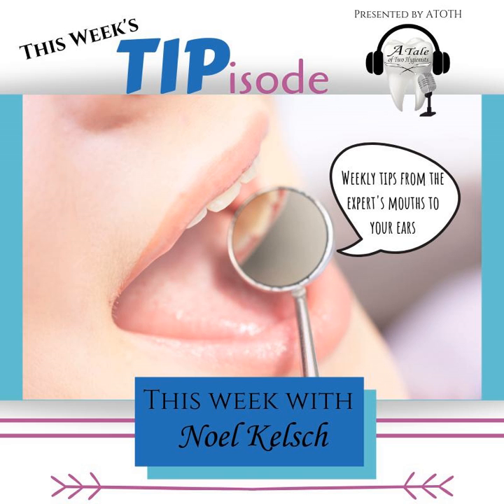So what is an ultrasonic? Well, deep inside your ultrasonic tank are ultrasonic transducers. These are placed according to the size and shape of the unit. These transducers create microscopic bubbles in the ultrasonic solution that is placed in the unit. The act of cavitation is that rapid formation and collapse of 1 million tiny bubbles in a liquid.